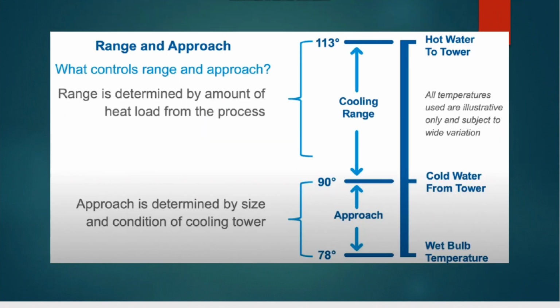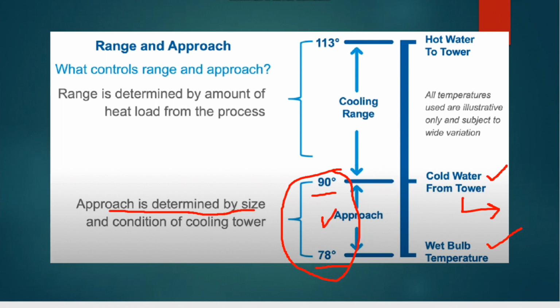This will give you some clear understanding. The ambient wet bulb temperature is 78 degrees Fahrenheit. The cold water from the tower to the chiller, after the process, is 90 degrees Fahrenheit, and the difference of these two is called the approach. The approach is determined by the size and condition of the cooling tower. So this parameter is very important to find out the size and condition of the cooling tower.